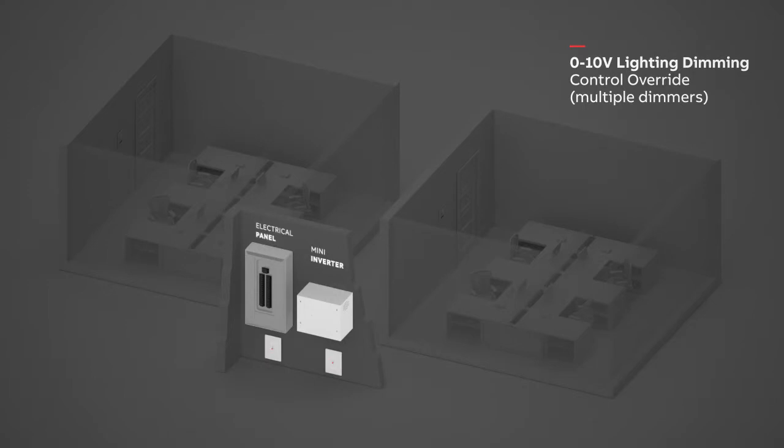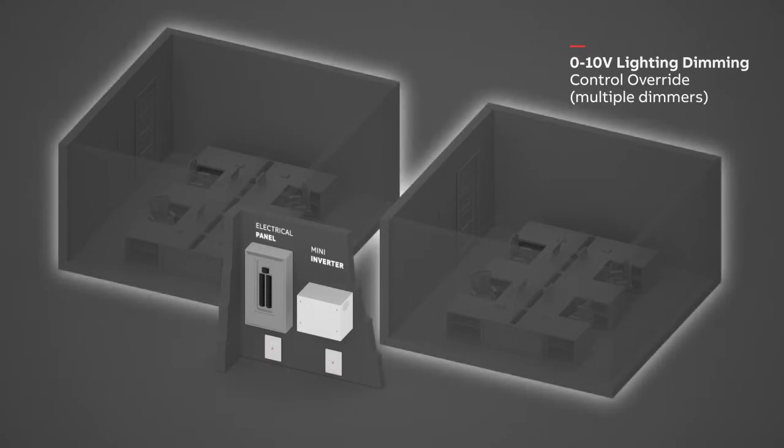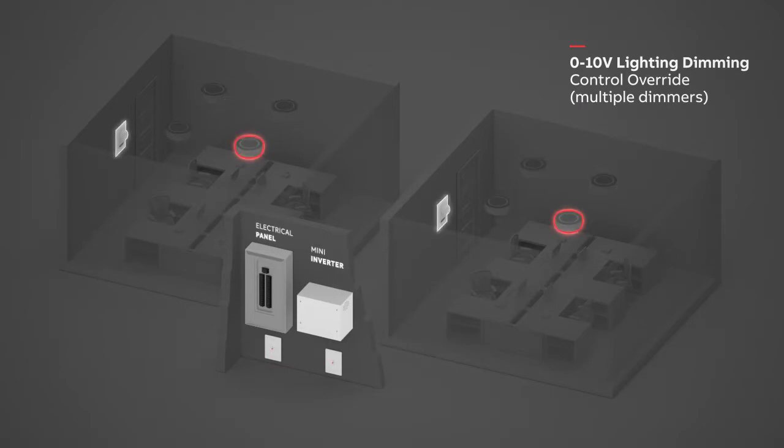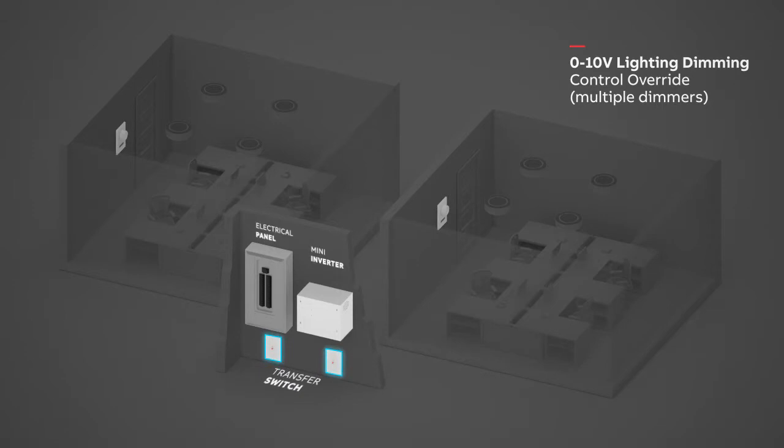In this example we have more than one zone. Each zone has multiple lights that are controlled by a dimmer switch, including an emergency light in each room. Since there is more than one dimmer switch that needs to be connected to the mini inverter, 0-10 volt compatible transfer switches must be used to override the lighting control devices.